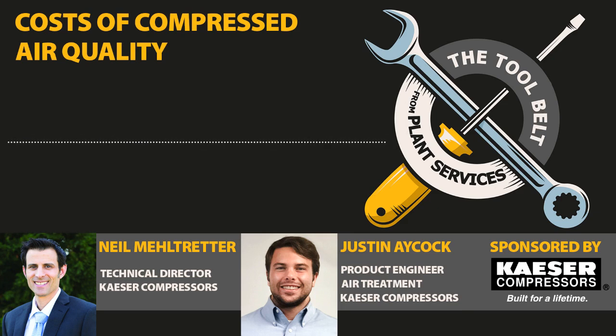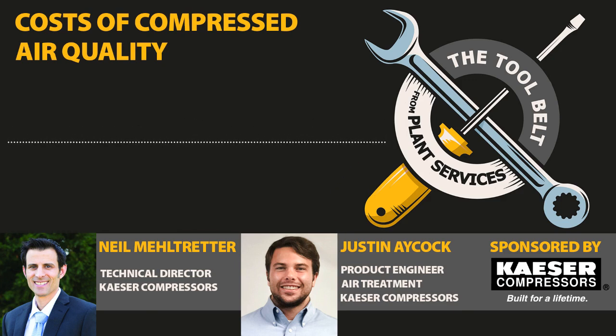So with that being said, you can have an air treatment system with multiple pieces of equipment and try to have the best insurance policy close to the ISO class, so you can have the correct quality air and then the best product in whatever you're using the air for. So for example, if you want an ISO class 1.1.1, you would use a high efficiency pre-filter to a desiccant dryer that's capable of reaching a minus 94 degree F dew point, then a particulate and adsorption filter after the dryer to give you the best air quality possible.